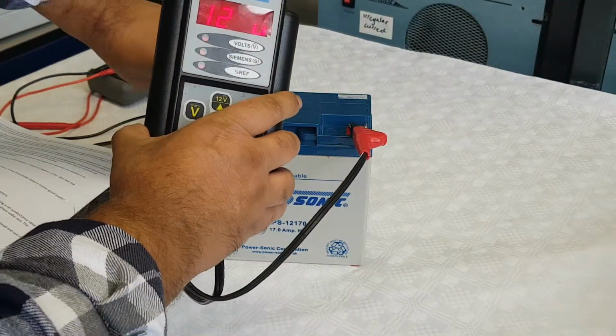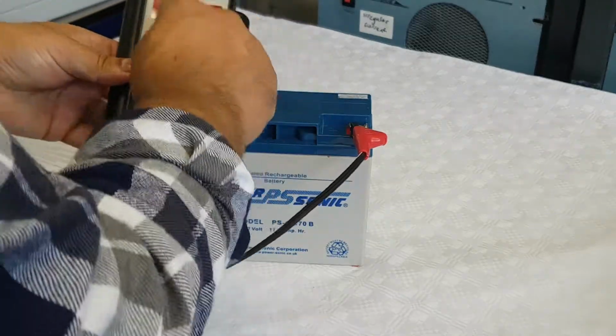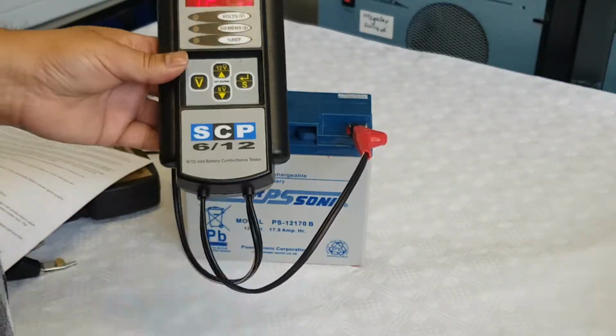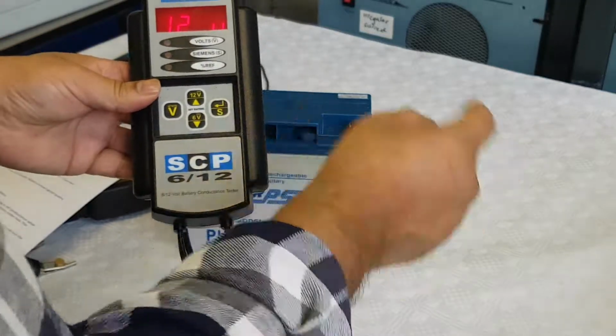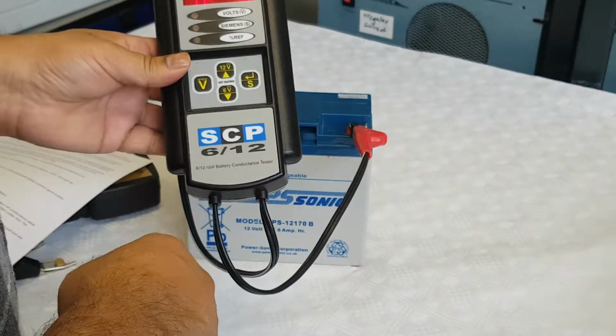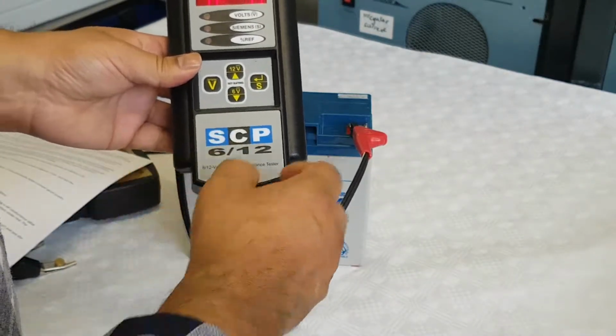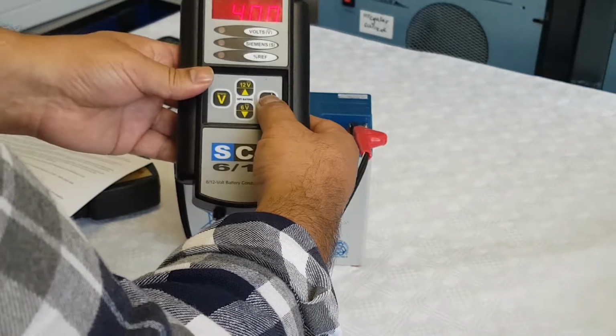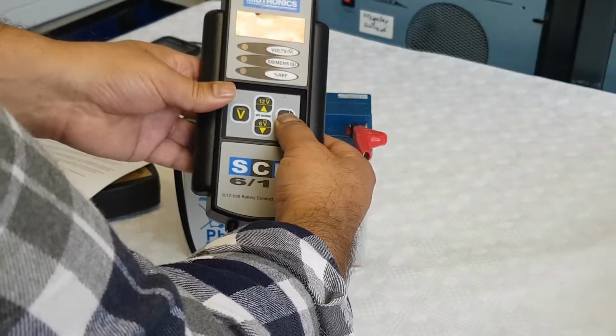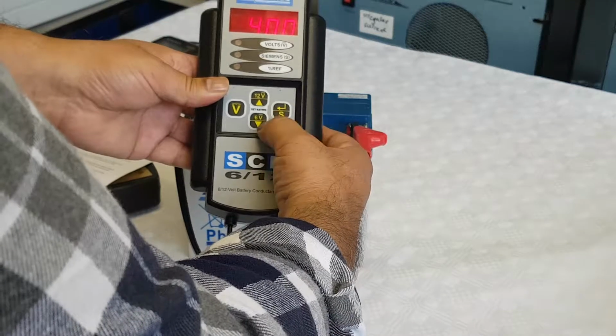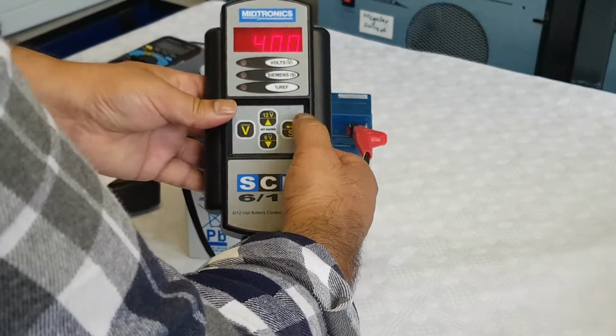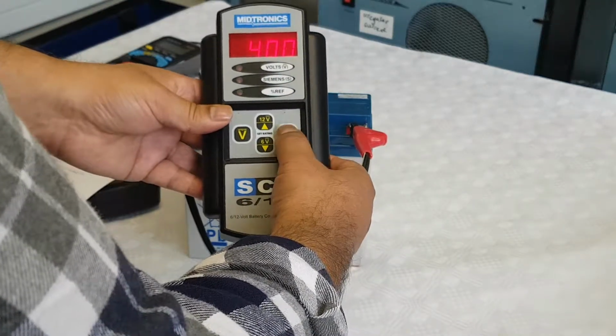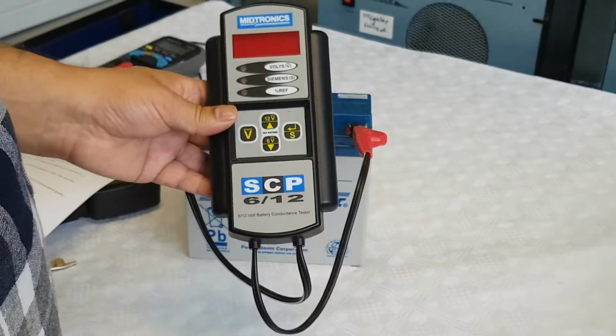Again, making sure we get good connections onto the terminals. It's a 12 volt battery, so it's been set at 12. Next thing, we've got to input the reference value. The reference value is 400, so we'll just check that first. Okay, it's already set at 400. So all we need to do next is just press S again and it'll start the test.